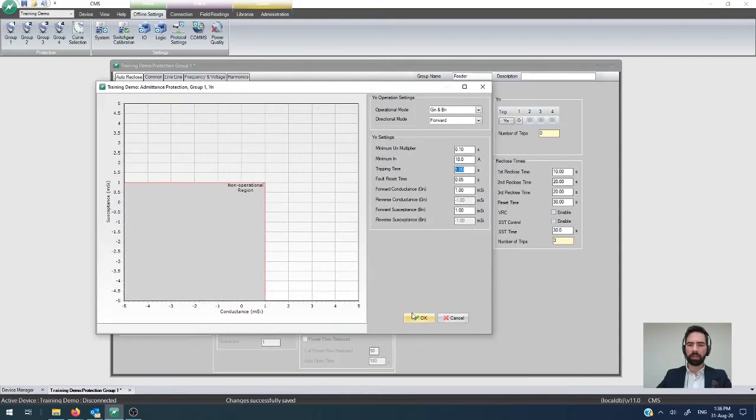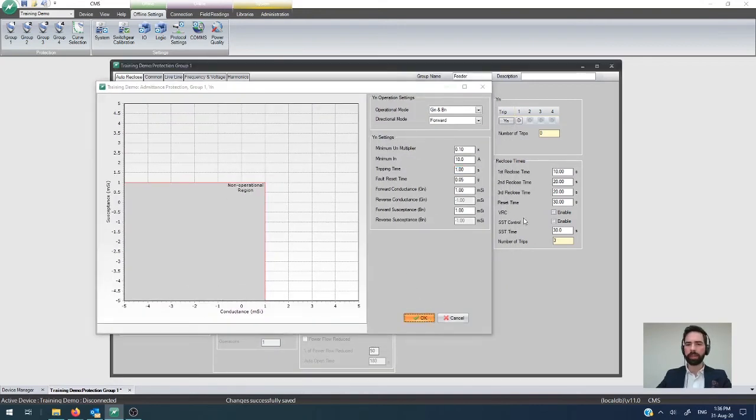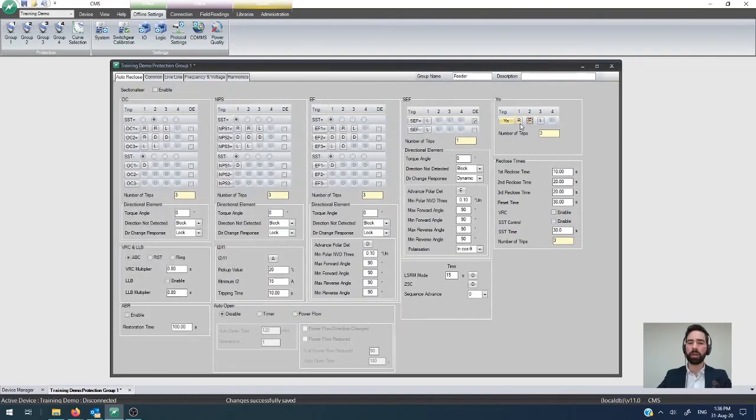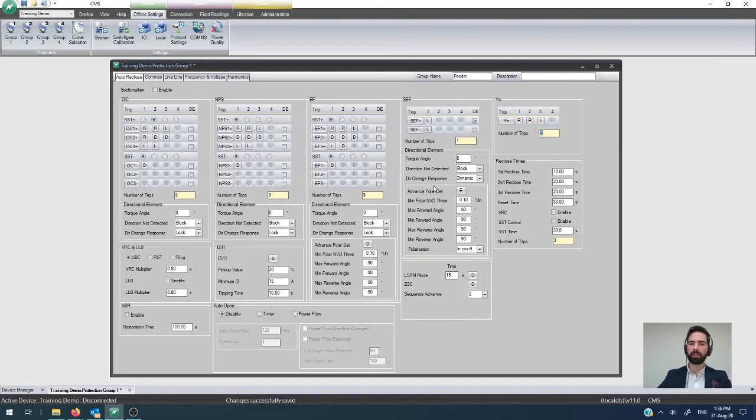Once you're satisfied that your settings are configured as to what you think they need to be then you simply click OK and I want to set it to do three shots to lockout so reclose, reclose, lockout and my number of trips down below says three shots to lockout which works out just fine.